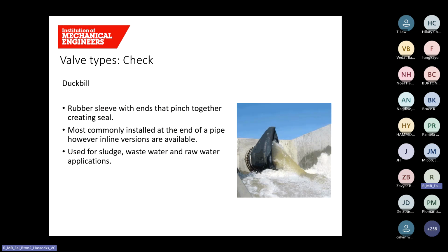Another check valve is the duckbill valve. This valve consists of a rubber sleeve which is curled up at the end, and when flow passes through it, it unfurls and the rubber sides separate, allowing flow to pass. As the water rises on the downstream side, creating a pressure differential, the valve then closes again. This valve is most commonly used on sludge or wastewater or even raw water applications, often seen at the coast at the end of a short sea outfall or a surface water runoff point. There are in-pipeline versions of this valve, but they're not as common. We don't tend to use them in the water industry.